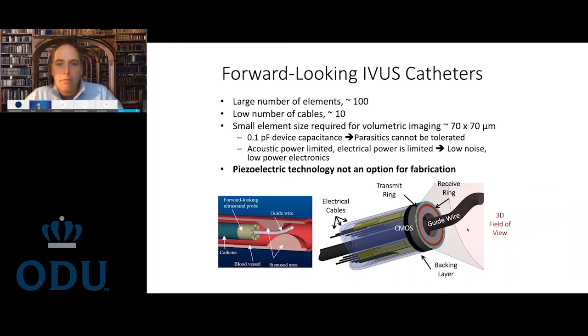We're looking at a very, very small donut with about 100 elements on it. If your cable is only 1.5 millimeters in diameter, the number of cables that can come out is very limited. That means you need to have elements up front, but you also need to have electronics, and we need low power, low noise.